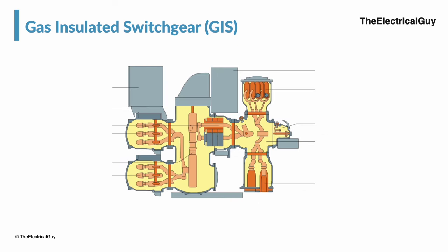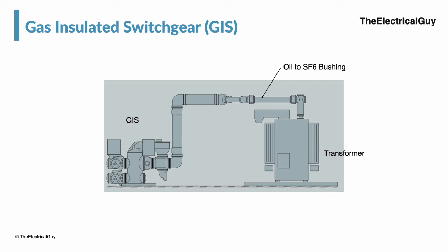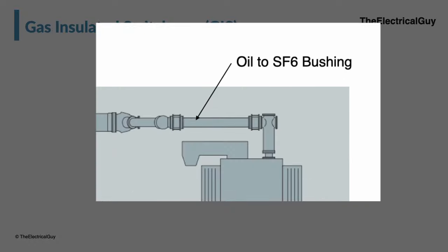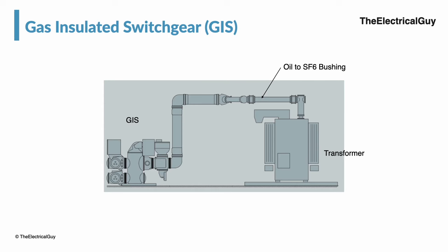Since all the switchgear are connected together and insulated with SF6 gas, direct connection of a transformer or overhead line is not possible. To allow the connection of transformer and incoming supply, we need to use bushings. It can be oil-to-SF6 bushings, which facilitate the connection between the transformer and GIS, or it can be an air-to-SF6 bushing, which allows the connection between an overhead line and GIS. Bushings are really important in case of GIS.